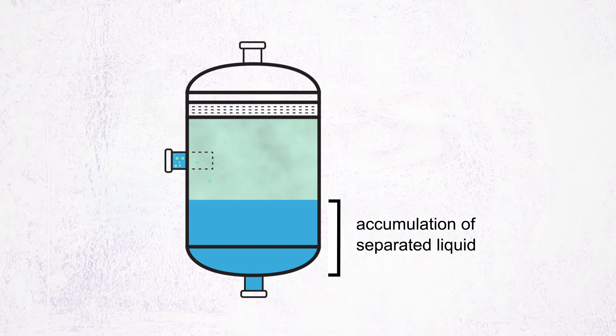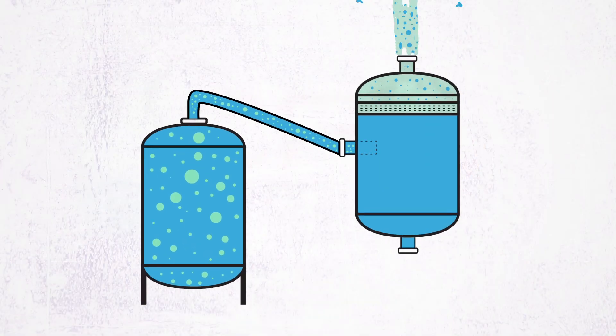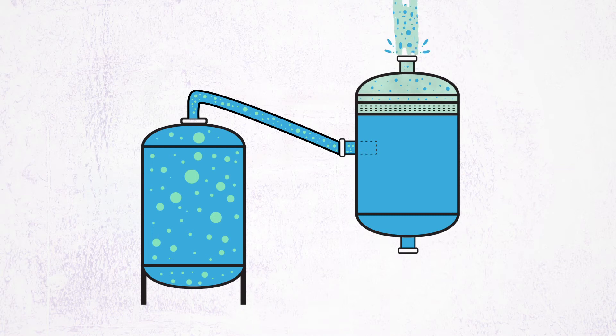A common mistake we come across is a knockout tank that is too small given the size of the relieving equipment and the reactive upset scenario. A knockout tank that is the same size as a reactor or storage tank is often not able to effectively do its job.